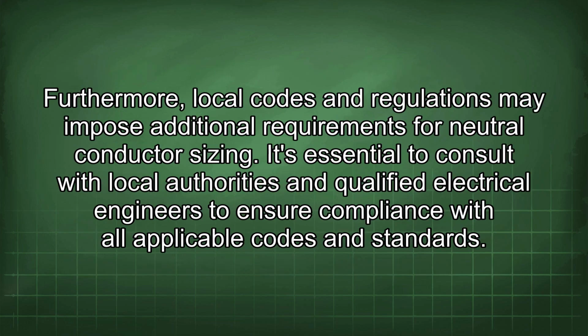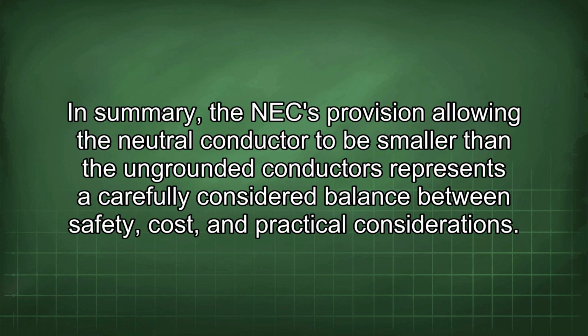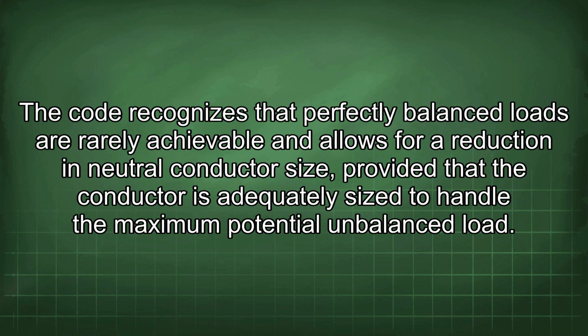Furthermore, local codes and regulations may impose additional requirements for neutral conductor sizing. It's essential to consult with local authorities and qualified electrical engineers to ensure compliance with all applicable codes and standards. In summary, the NEC provision allowing the neutral conductor to be smaller than the ungrounded conductors represents a carefully considered balance between safety, cost, and practical considerations. The code recognizes that perfectly balanced loads are rarely achievable and allows for a reduction in neutral conductor size provided that the conductor is adequately sized to handle the maximum potential unbalanced load.